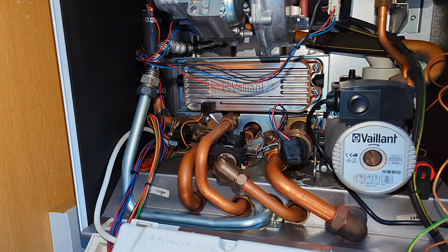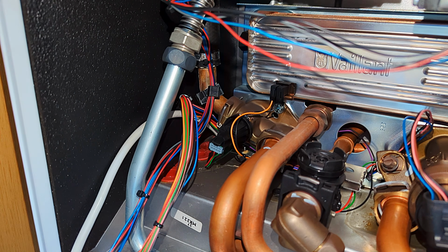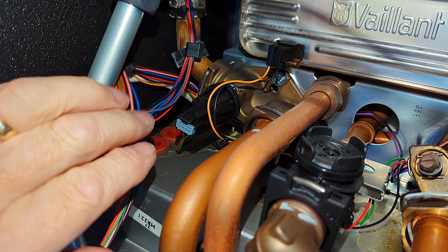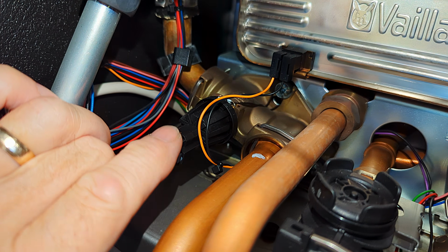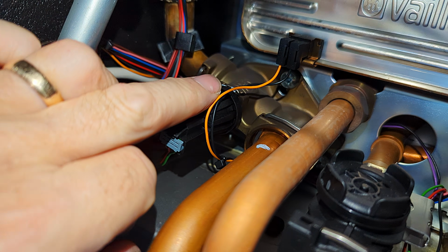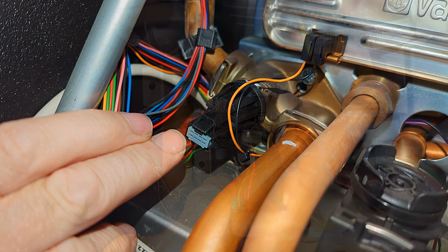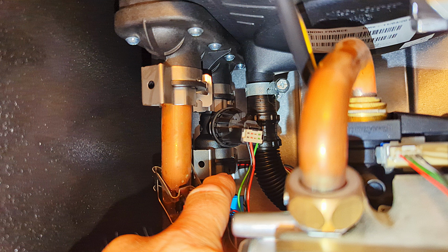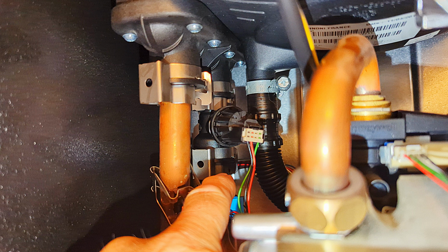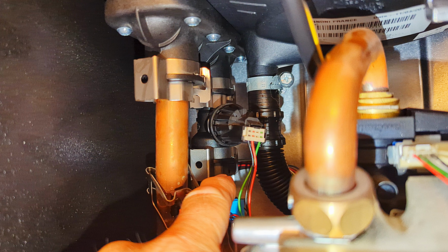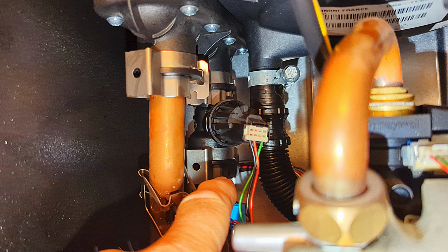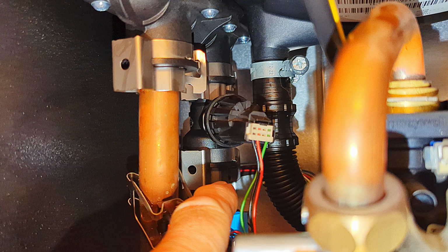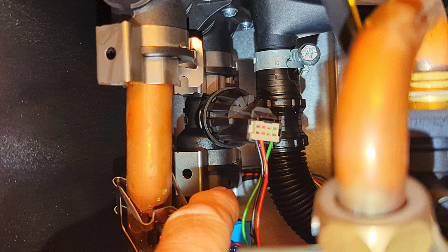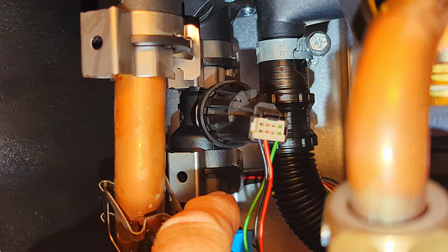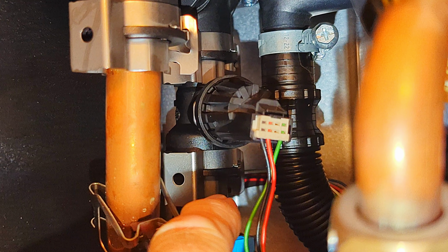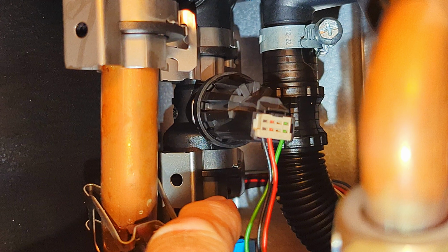If your pressure sensor is at the bottom of the boiler, which is after the main heat exchanger, you can move it to the top of the boiler, so it's then before the main heat exchanger and directly after the pump, which is obviously much better. But that's providing the new pipework is installed in the boiler. If you have this plastic part on the pipework which the pressure sensor goes into, and there will be a brass plug in that position. So it will be just a case of removing the brass plug and fitting the pressure sensor in its position and putting the brass plug in the pressure sensor's position at the bottom of the boiler.